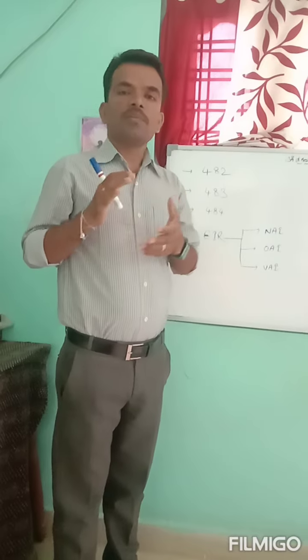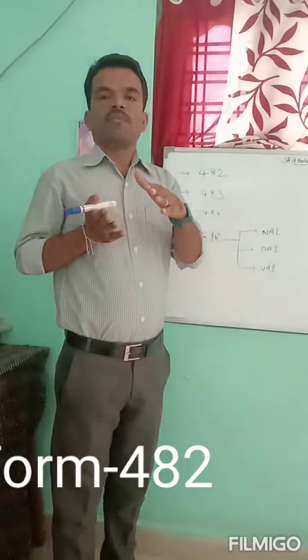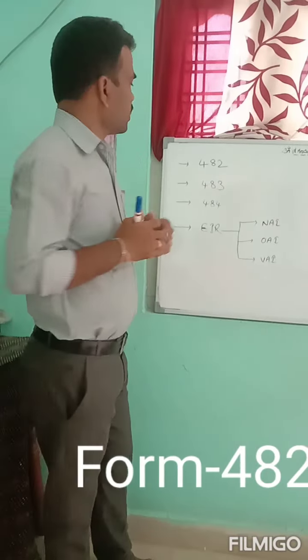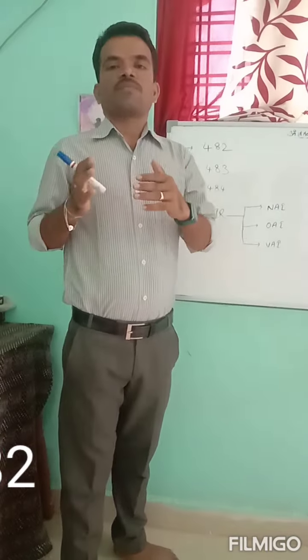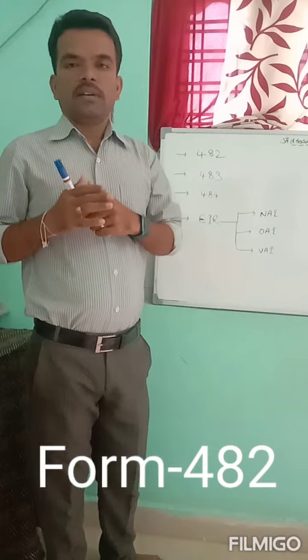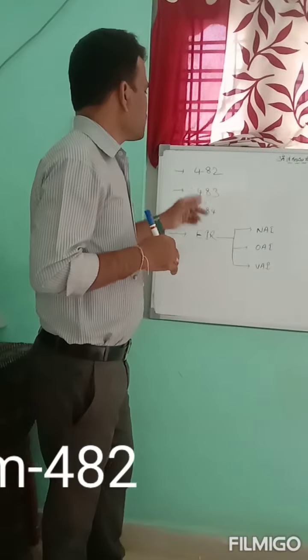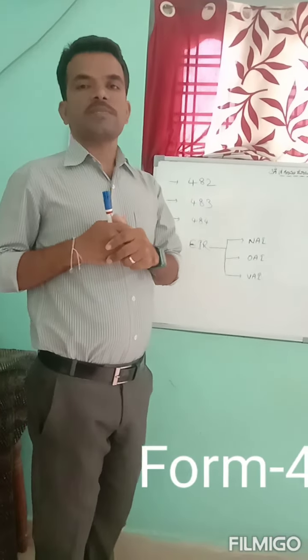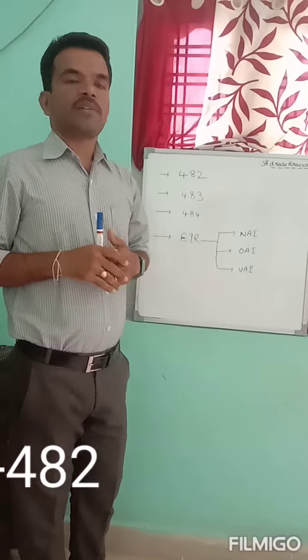But here there is no limit. Initially they will mention that they are going to inspect your site for 5 days, but after 5 days there is a chance to extend the inspection time. This 482 is related to the pre-intimation form issued before they go to inspect the audit site. As per FDA section 704, this 482 will be given before going to the inspection of the manufacturing site.